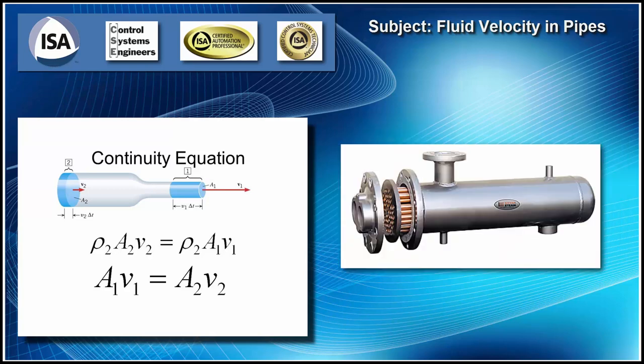In other words, if you're trying to transfer heat like we talked about in thermal, and we're trying to use a heat exchanger, first of all, we're going from a big pipe to a bunch of small pipes, so we don't want our velocity too high. It'll vibrate these pipes and crack the weld. The other thing is when we go slower, it's much easier to transfer the energy from one fluid to another fluid at a lower flow rate. It's easier to absorb that energy and heat.